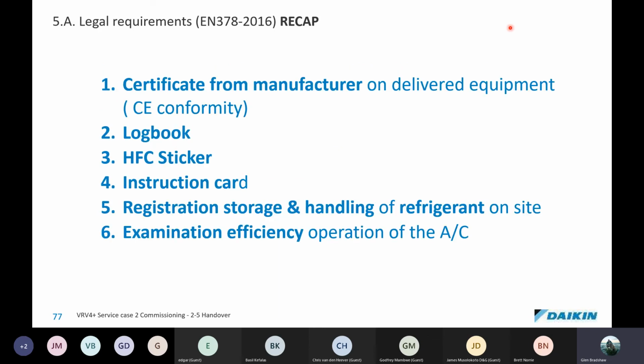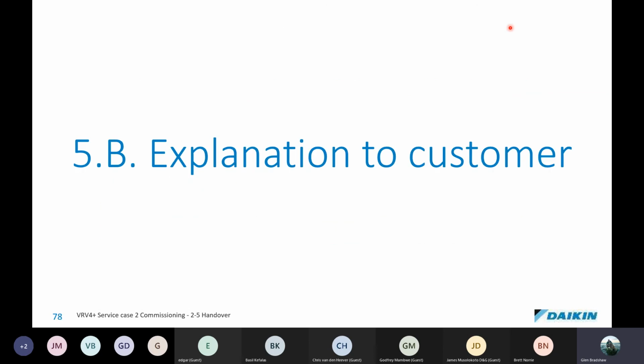Okay, a certificate from the manufacturer on delivery of the equipment. Sometimes we have to give that. A logbook should be handed over. The HFC sticker should be put in place. Instruction card for operation. Registration on the storage and handling of refrigerant on site. I know that a lot of your bigger users of air conditioning are now required to keep a register which gives the total amount of specific refrigerants that they have on site. I know that I've worked with pharmaceutical companies where that is updated on a regular basis. And then the examination of efficiency of the operation of the air conditioning system, which is part of the service function, and is something that you can obviously charge for as well.